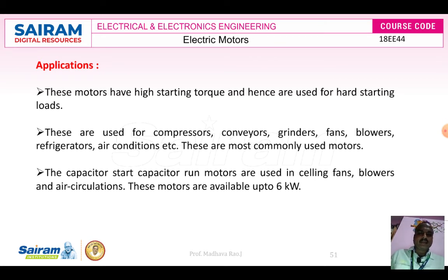Capacitor start and capacitor run motors are especially used in ceiling fans, blowers and air conditioners. The availability of these motors is up to 6 kilowatt. More than that, single phase induction motors are not available and also not suitable for applications above the 6 kilowatt range. So we need to use 3-phase induction motors, whose construction is very strong and rigid and whose maintenance is less compared to single phase induction motors.